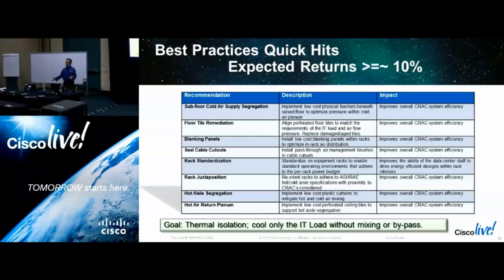So you look down there for obstructions under the floor. You know, a legacy water pipe on a mainframe, whatever. If you have a mainframe and it's pipes down there, it is what it is. But to the best of our ability, we don't have obstructions down there. It's not trash or whatever. It's clean, it's straight. Put the tile back in the floor when you're done. Don't create holes for other people to fall into.